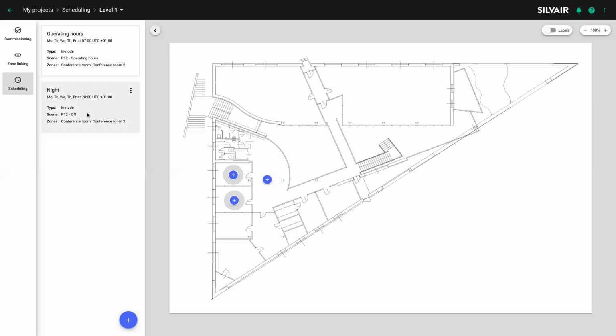We can have up to 16 events per zone, that means per those zones that have this particular profile. If we want to have different schedules, we need to create additional profiles and apply them to the zones where we would like to have separate scheduling.